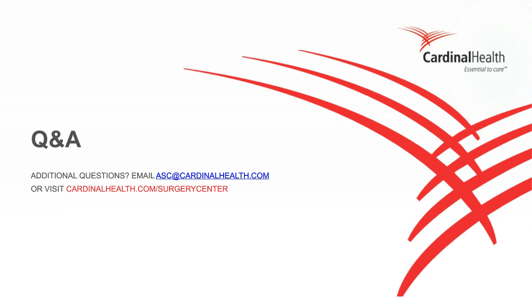So I'm going to assume that it's an ASC related question, and it's a good question because PCI procedures are pretty difficult to do on a mobile C-arm. We see some folks doing it with a flat detector mobile C-arm, but the imaging capabilities are really limited. So it's going to be a fixed base system, and you can have both a ceiling mount and a floor mount option. That's going to be your most costly piece of equipment. With that comes the floating table that's radiolucent. That whole setup is anywhere between, on the lowest used refurbished market end, probably $500,000, up to over $1 million.